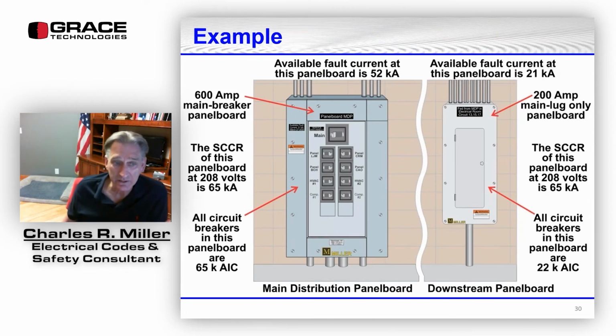This Miller brand switchboard, this Charles R. Miller, which is again a Cadillac of equipment. The available fault current at that panel board is 52 kA. There's a 600 amp main breaker. The short circuit current rating of that panel board is 65 kA. All breakers in that panel board have an interrupting rating of 65 kAIC.